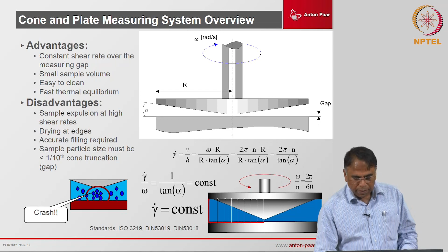The only disadvantage in the cone and plate is that if you have samples with big particles, then it is not possible to measure. The reason being, ideally a cone would have a very sharp tip at the center and the tip would actually touch the bottom plate. But if you manufacture that cone in that way and the tip is touching, then we will start measuring the friction between this touching point of the cone and the plate. So, what we do is we trim off this tip, and whatever we trim off, that is measured, and that will become our gap.